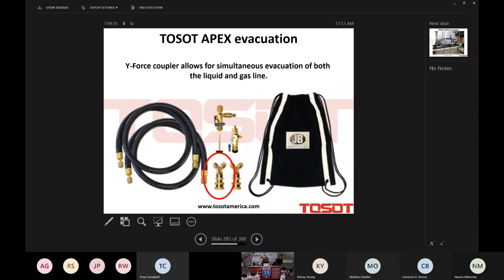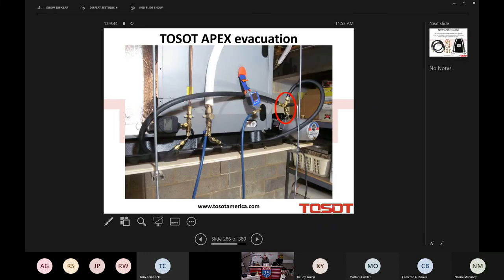The beauty of these Y fittings that come with this, I think it's called the Evacuator, don't hold me to that. These Y fittings allow you to do this. Look at this. Because we had to pressure test each line set separately, again, we don't have an open end on either end. Each coil is charged. As a result, we have to leak test separately. We also have to evacuate separately. But the beauty here with that Y-shaped fitting, I can do both line sets simultaneously.